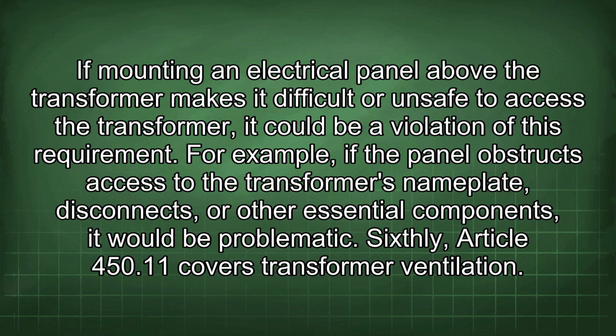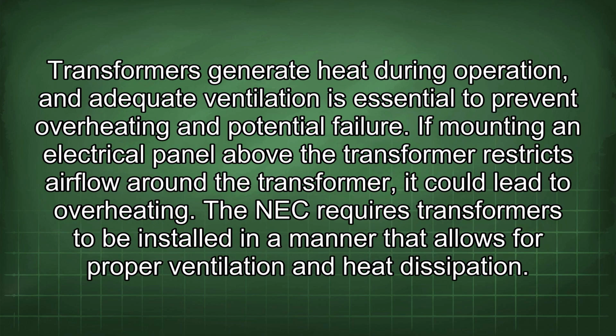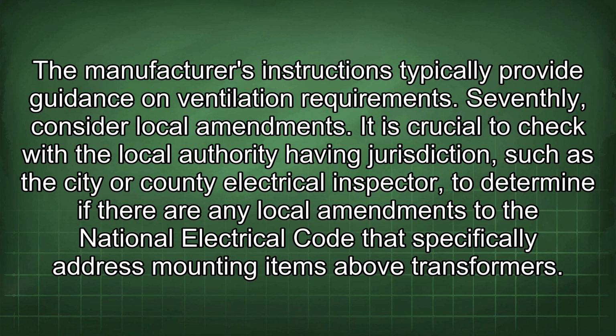For example, if the panel obstructs access to the transformer's nameplate, disconnects, or other essential components, it would be problematic. Sixthly, Article 450.11 covers transformer ventilation. Transformers generate heat during operation, and adequate ventilation is essential to prevent overheating and potential failure. If mounting an electrical panel above the transformer restricts airflow around the transformer, it could lead to overheating. The NEC requires transformers to be installed in a manner that allows for proper ventilation and heat dissipation. The manufacturer's instructions typically provide guidance on ventilation requirements.